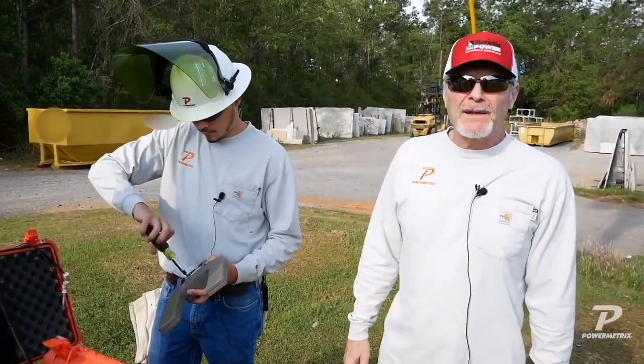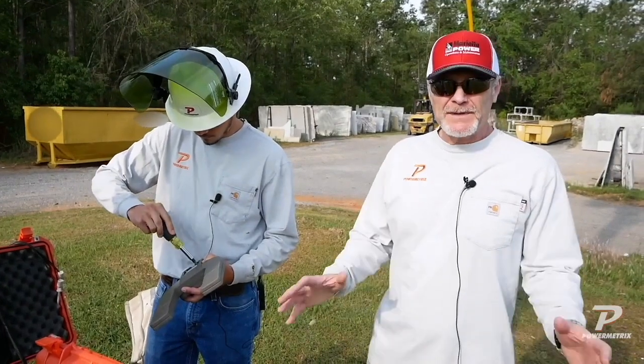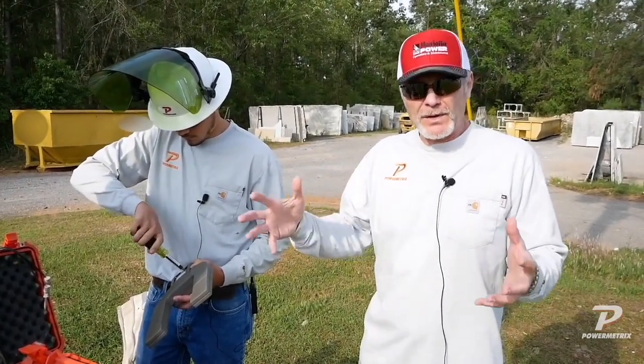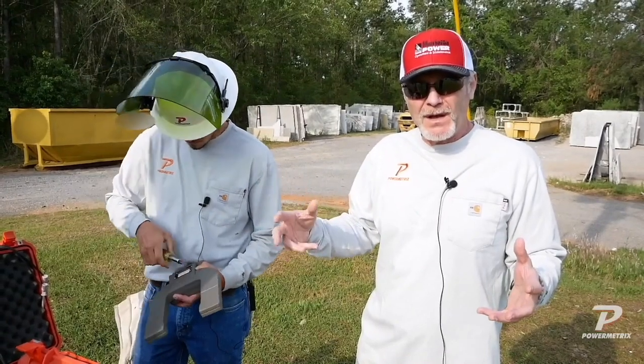By the end of our testing yesterday, Browlin noticed something, and any tips or training we can give, we always do. We noticed that on the time delay of the high volt probe, normally you can set it for a longer delay so it stays powered up before it turns off. In this case, it wasn't staying on as long, it started shutting down earlier, which indicated the battery might be going down on it.